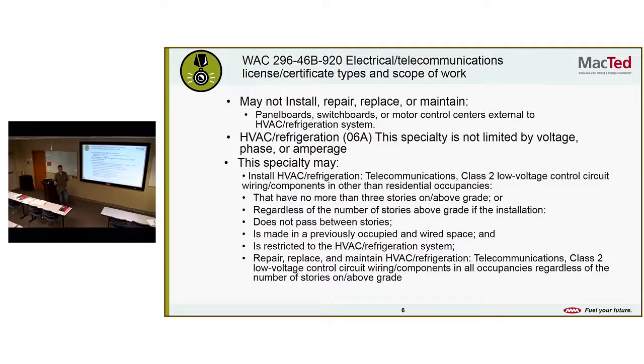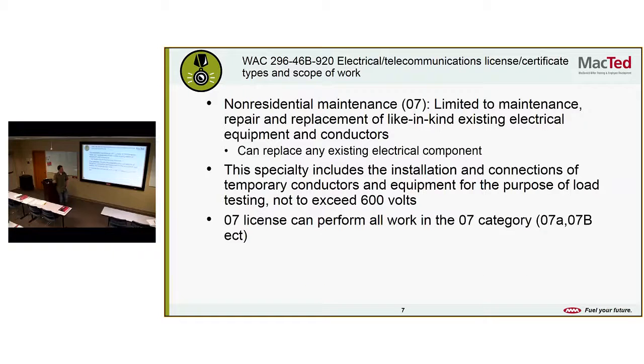So long story short, I'd recommend everybody that currently has an 06A get an 07. With an 07 you can replace line voltage outside the box. With an 06A you cannot. The only line voltage component you can do with an 06A is the whip, and you can maintain that disconnect that the whip's attached to if it's within line of sight of the condensing unit or that piece of equipment, and under 6 feet. Exactly. The 07 opens up what you can work on. So they're a nice complement to each other. Any questions on those?